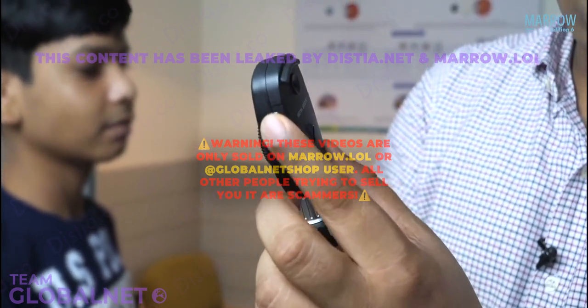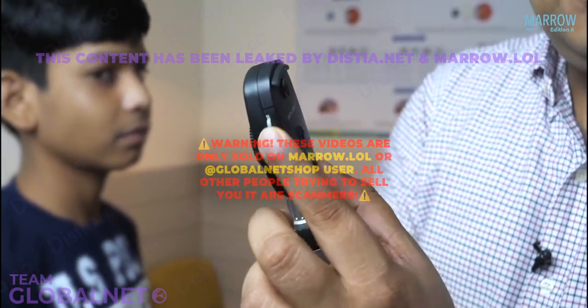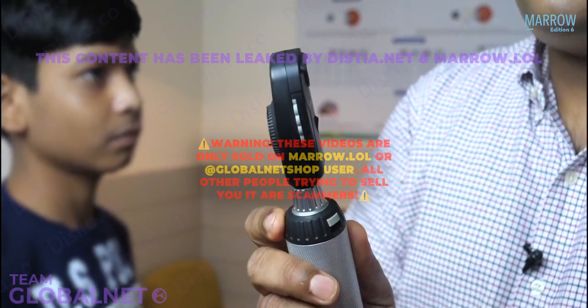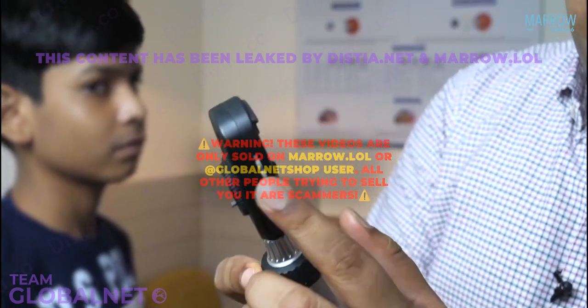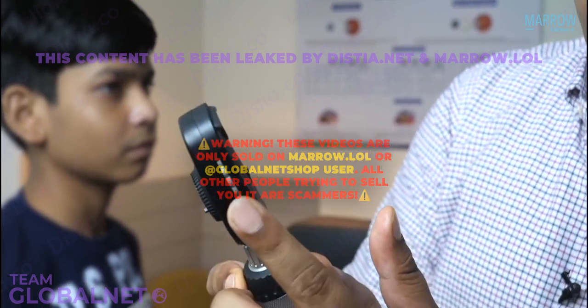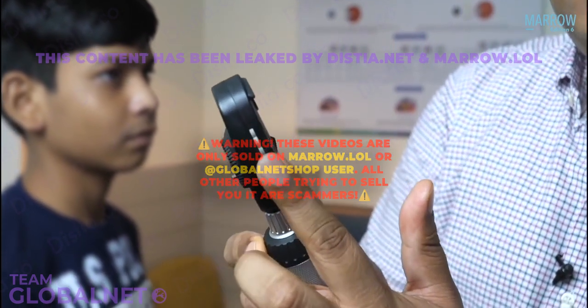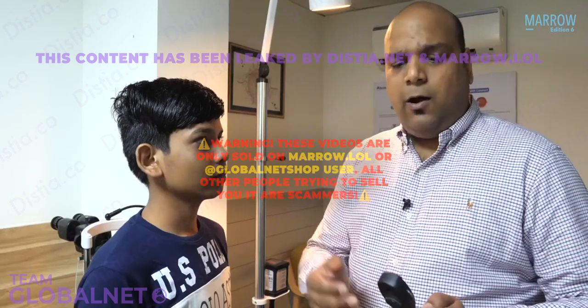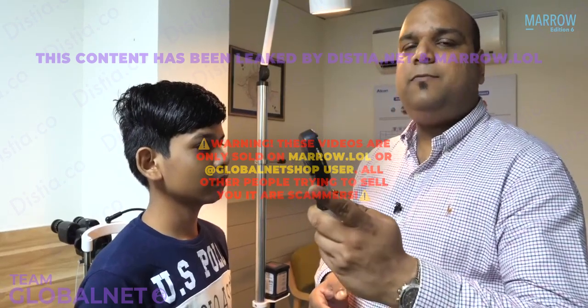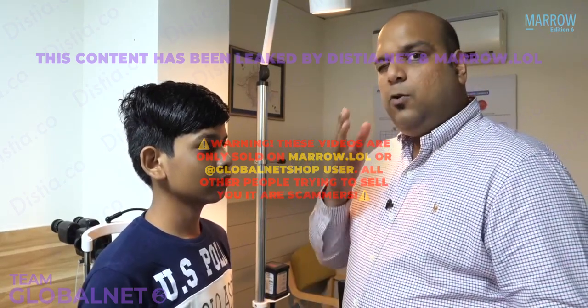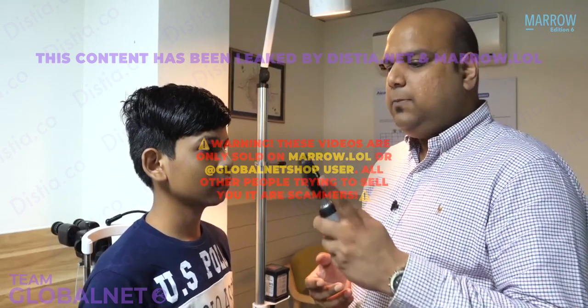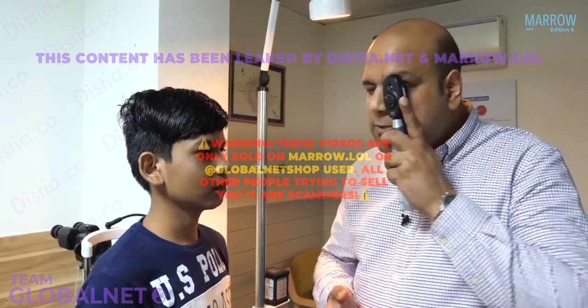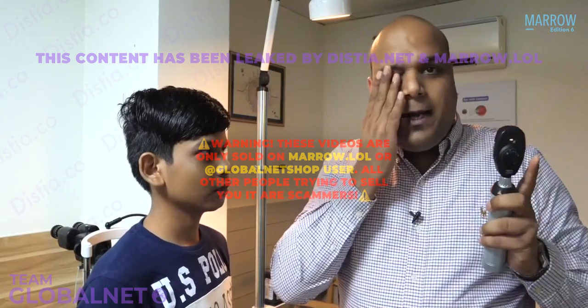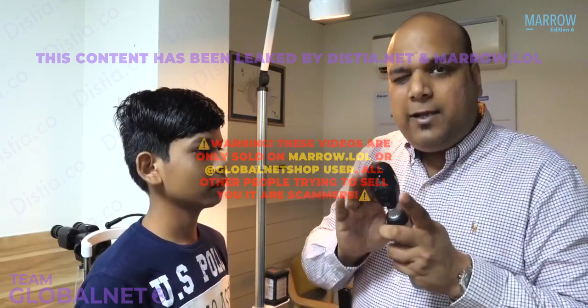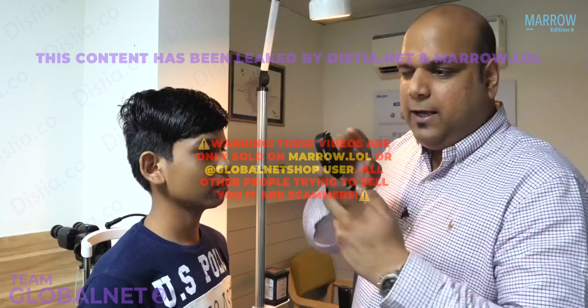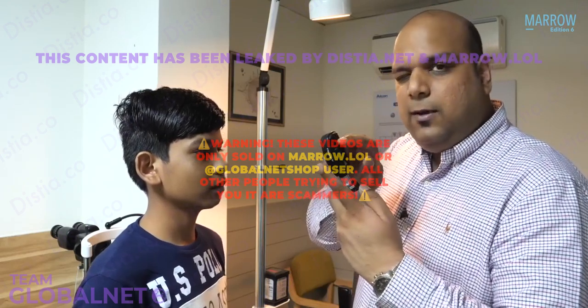This regulator changes the power of the lens. That is why we saw that in the indirect ophthalmoscope, we were holding a 20 diopter lens, but in this, we don't need any other lens. We can change the power of the lens through this turn, everybody. Okay. So now, how do we use this instrument to examine the fundus of the patient? We close one of our eyes. We keep the instrument over one of our eyes. So if you look at me now, my right eye is closed and my left eye is open. The instrument goes over my left eye in front of this hole.